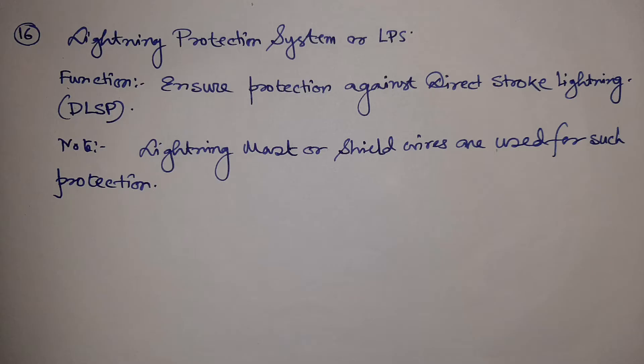Our first system is the lightning protection system. It is not an equipment but a protection system to protect the substation against direct stroke lightning. For indirect lightning there is a lightning arrestor or surge arrestor, but for direct lightning the lightning protection system has to be used. It is generally constructed by a lightning mast or shield wire, which arrests the lightning surge and sends the discharge current to the ground.